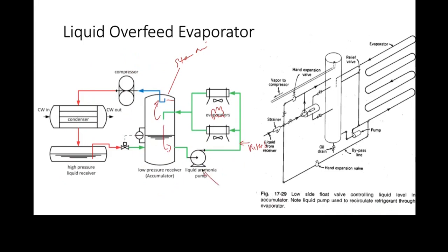And then what we have is, this is a controlled circulation type of boiler, so it's got some forced circulation. So really, it's very much like a boiler. And of course, we need to have feed water. So we've got a single element feed refrigerant control, and we've got an on-off two-position single element feed water, or feed refrigerant, solenoid. Okay, it's like a boiler.